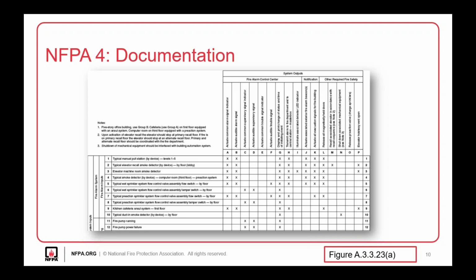And the test report should include the test plan, an input-output matrix, sequence of operations, an issues log, and a corrective action report. Additional test documentation might be required by the insurance representative or maybe the AHJ, such as the local building or fire department. The integrated testing agent should be in communication with those entities throughout the process. So as Jacqueline talked about, getting that AHJ involved early about any special reporting requirements that they have up front.